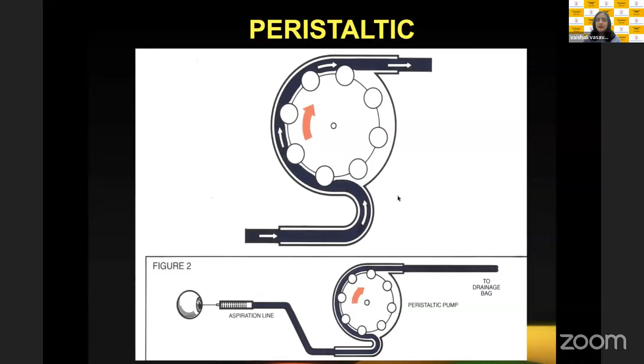Let's understand the 2 important parameters, flow rate and vacuum. What is the aspiration flow rate? It is the speed at which the fluid moves through the aspiration tubing. That is measured in milliliters per minute, or cc per minute. So if I say 20 cc per minute, in 1 minute 20 ml of fluid is being removed from the eye through the aspiration tubing. If I say 40 cc per minute, it goes to 40 ml. So much more fluid is being removed from the eye every minute. And like I said, it's measured in ml or cc per minute.